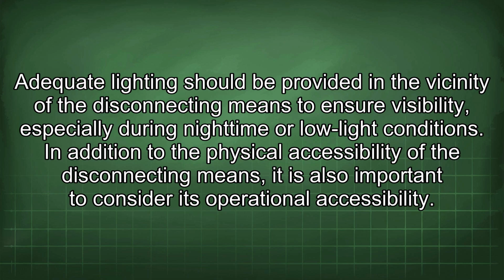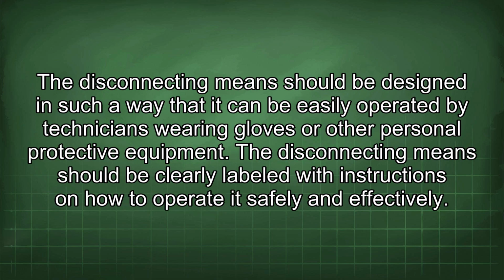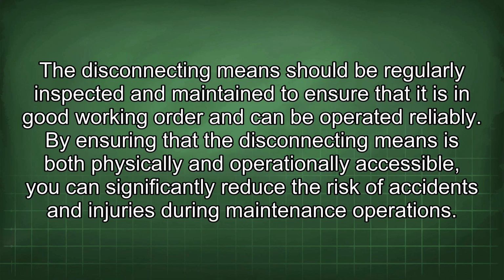Adequate lighting should be provided in the vicinity of the disconnecting means to ensure visibility, especially during nighttime or low light conditions. In addition to the physical accessibility of the disconnecting means, it is also important to consider its operational accessibility. The disconnecting means should be designed in such a way that it can be easily operated by technicians wearing gloves or other personal protective equipment. The disconnecting means should be clearly labeled with instructions on how to operate it safely and effectively. The disconnecting means should be regularly inspected and maintained to ensure that it is in good working order and can be operated reliably. By ensuring that the disconnecting means is both physically and operationally accessible, you can significantly reduce the risk of accidents and injuries during maintenance operations.